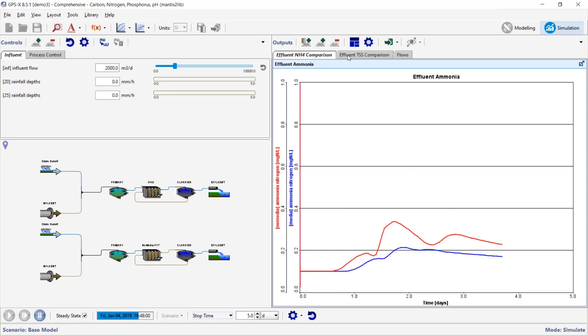In these comparison graphs, red is the regular plug flow tank with no media and blue is the IFAS system. Both receive identical influent. You can see that having the media does have an effect — the IFAS system shows a little bit of protection during the storm event. Having at least some biomass growing on the media helps because that biomass doesn't get washed out, even when flow peaks during the storm.